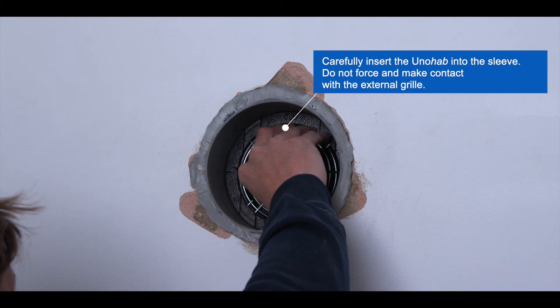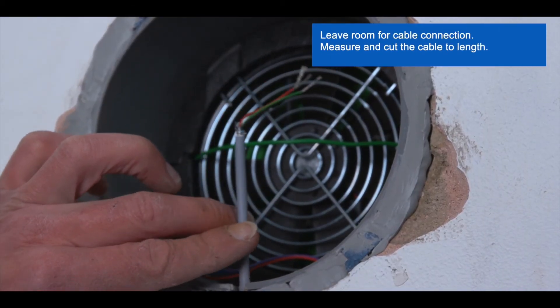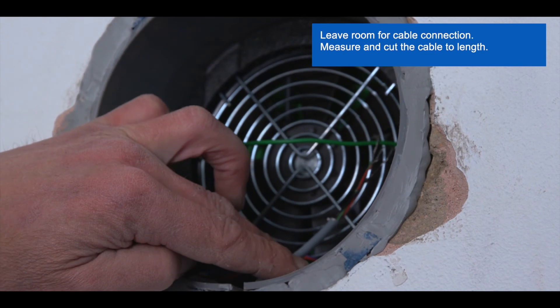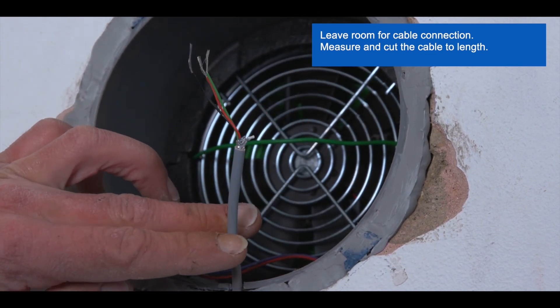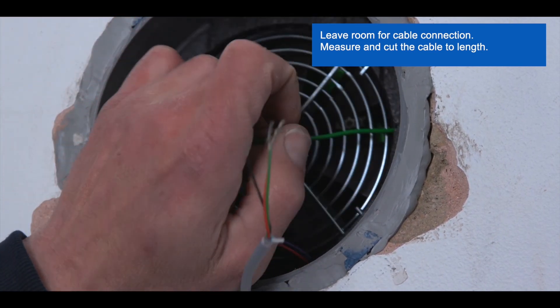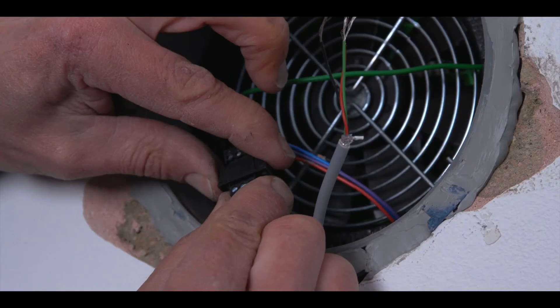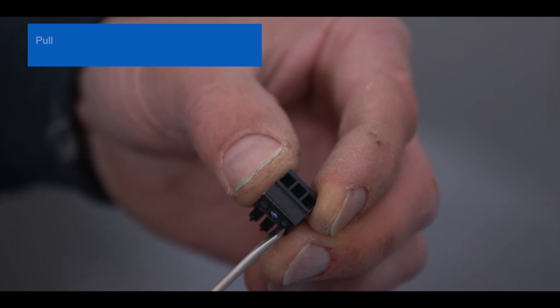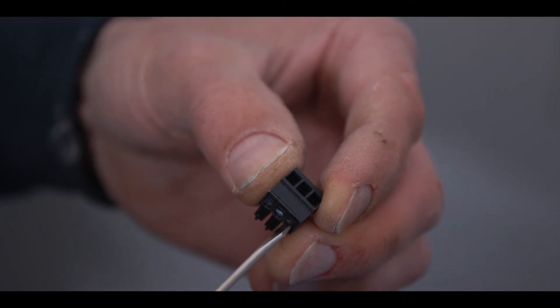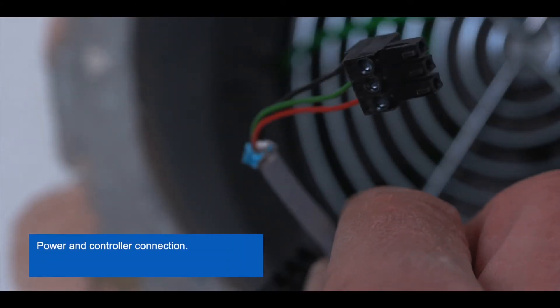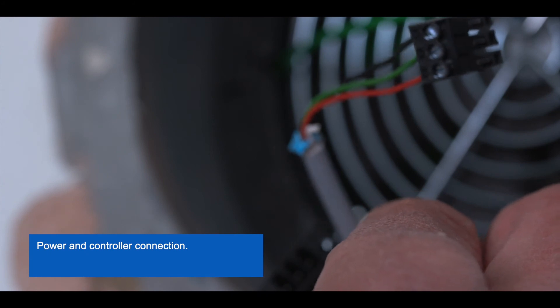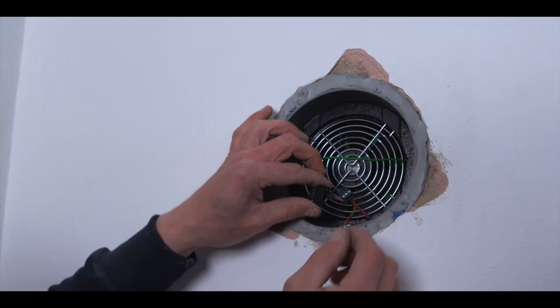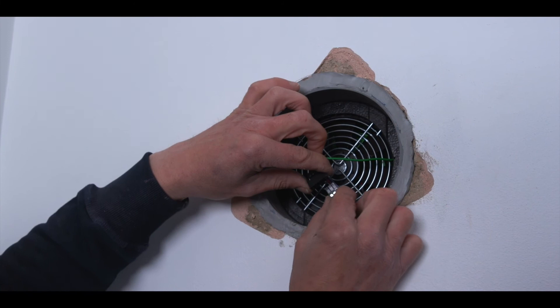Ensure you have sufficient length of cable. Measure and cut to length if necessary. Wire the controller cable as per the wiring diagrams which can be found in the Unohab unit manual. Please note the maximum distance between the Unohab controller and the unit is 30 meters. Once wired, plug the two-part connector back in and stow the connection cable in the allocated shell space.